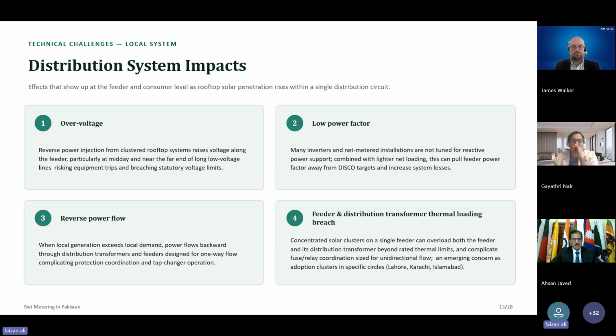With the overvoltage in place, you will see that many inverters and net meter installations are not tuned for reactive power support. Combining this with lighter net loading and more reverse power flows, you will see that the power factor starts to decline. Ideally, the power factor should operate close to 1, in the range of around 0.8 to 0.9. I'll show in my next slides how low it can go.